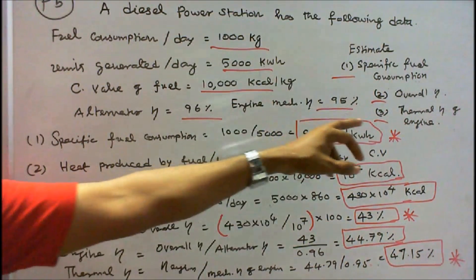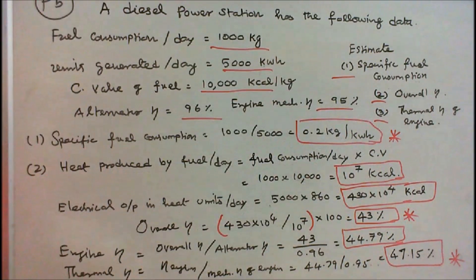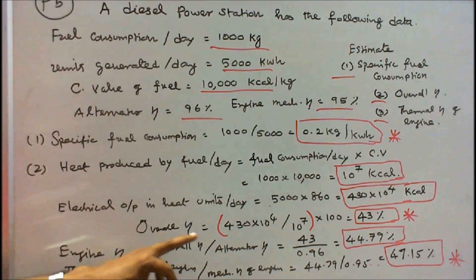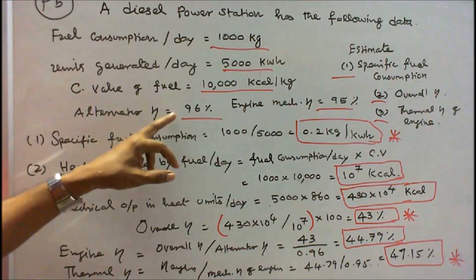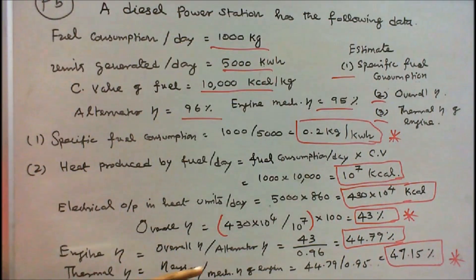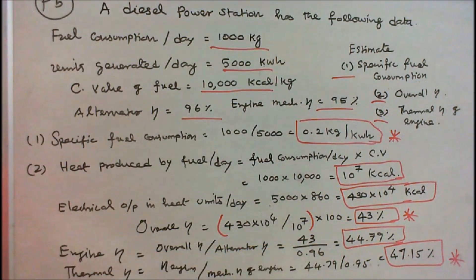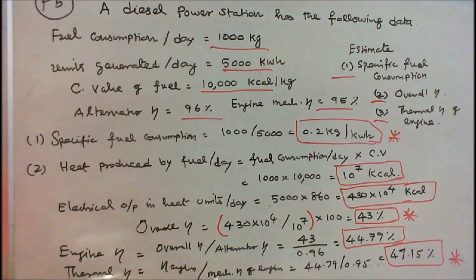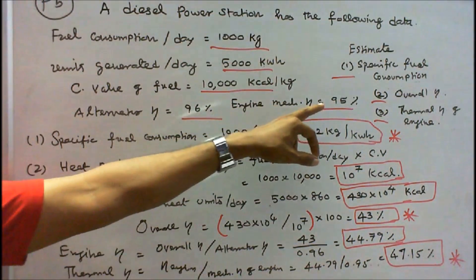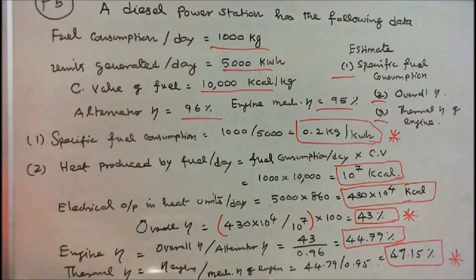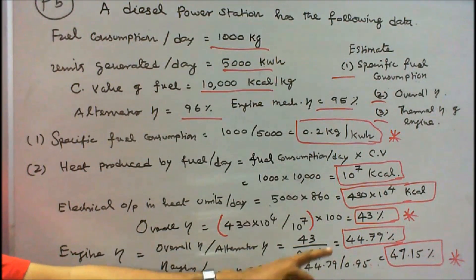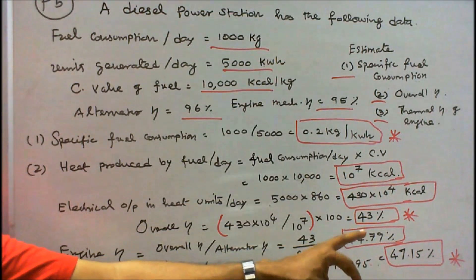Third: thermal efficiency of the engine. Engine efficiency = overall efficiency ÷ alternator efficiency = 43 ÷ 0.96 = 44.79%. Thermal efficiency of engine = engine efficiency ÷ mechanical efficiency of engine = 44.79 ÷ 0.95 = 47.15%.